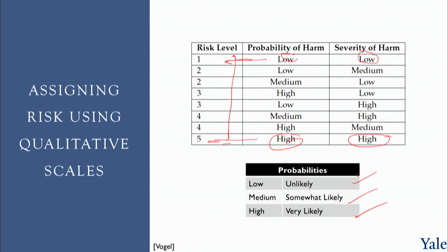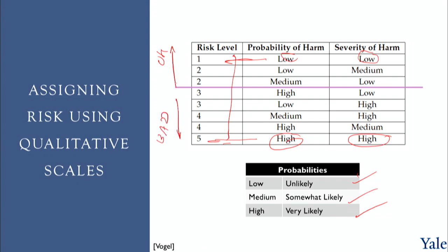Now, when we start a project, one of the things we have to decide on early is what is the acceptable risk in this project. So it may be, depending on the application, that we could say, well, risk levels below 2 are okay, and risk levels above 2, we'll call them bad here. And so we work through, we assess the risk involved in every possible harm. If it's less than 2, if it's 2 or 1, we say, that's okay, we'll document. It means we talked about this, we're done. And if it's more than 2, now we work out through techniques to reduce the risk, and we're going to talk about risk control techniques in the next segment.